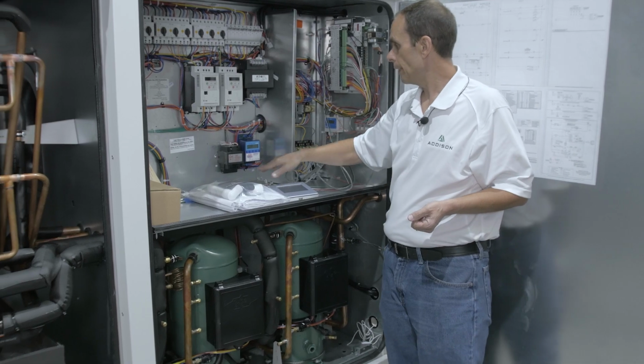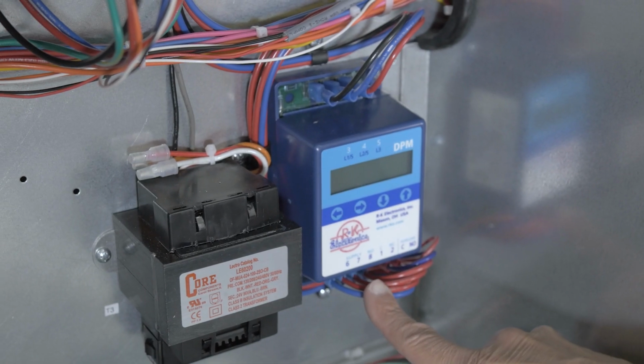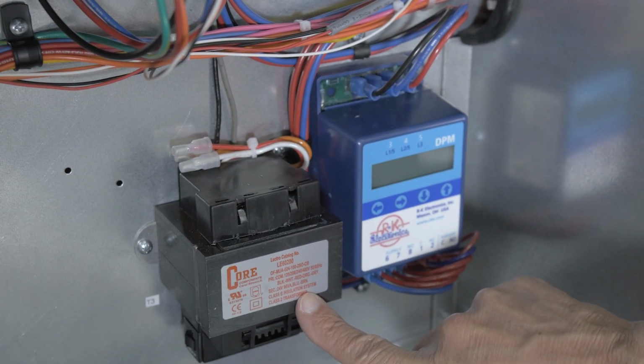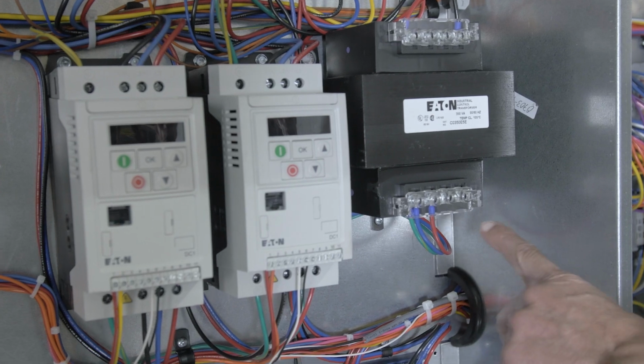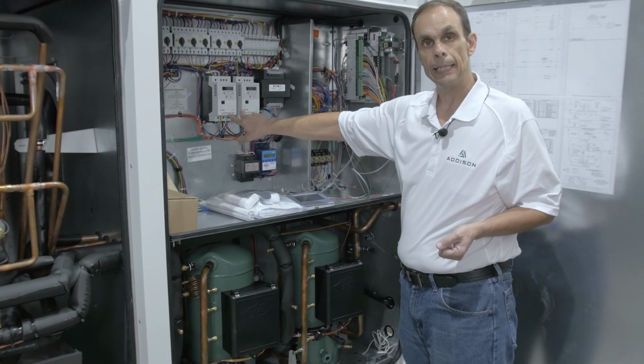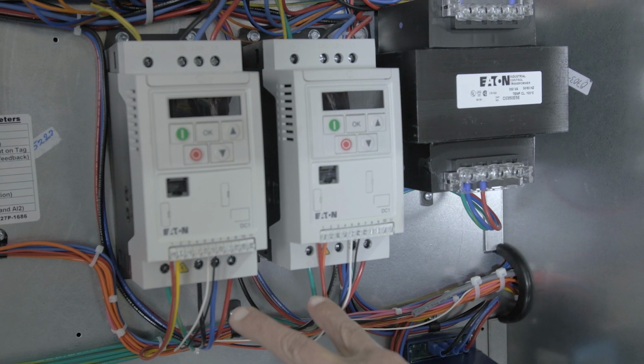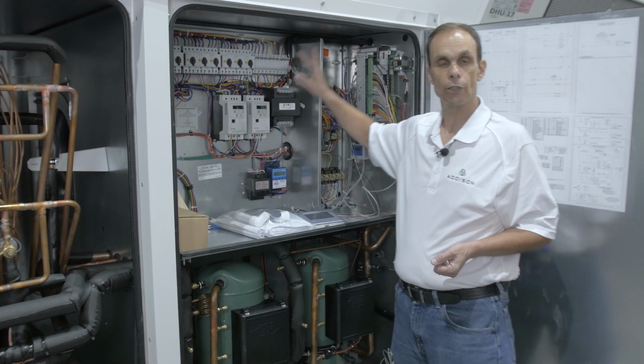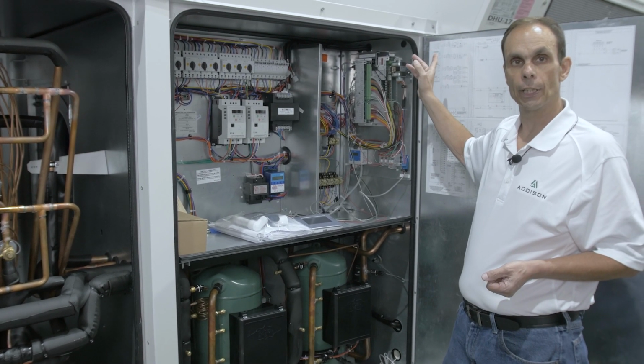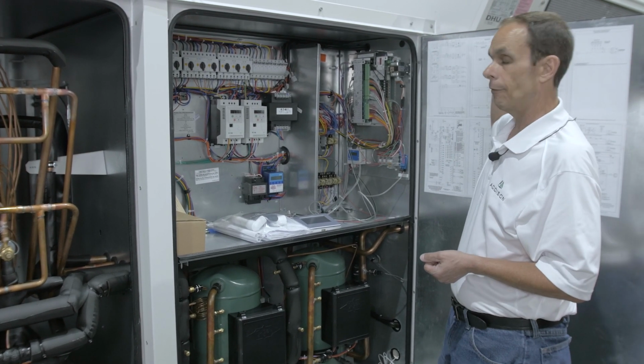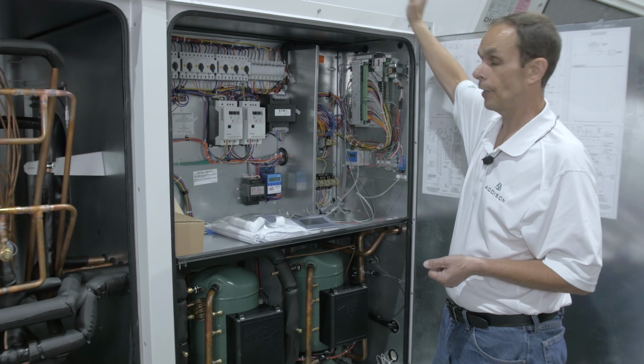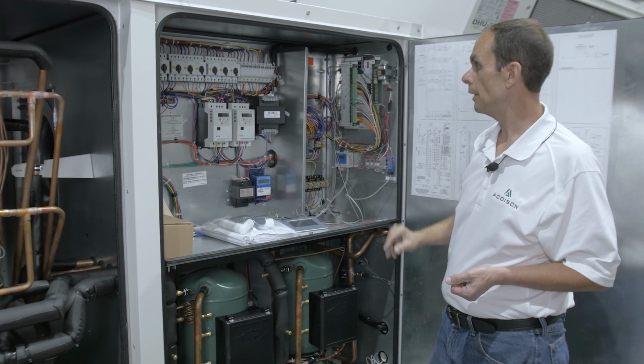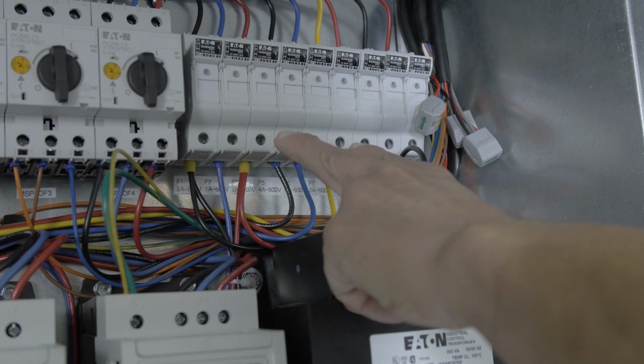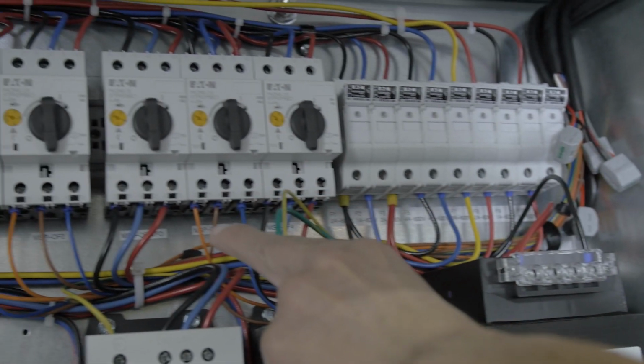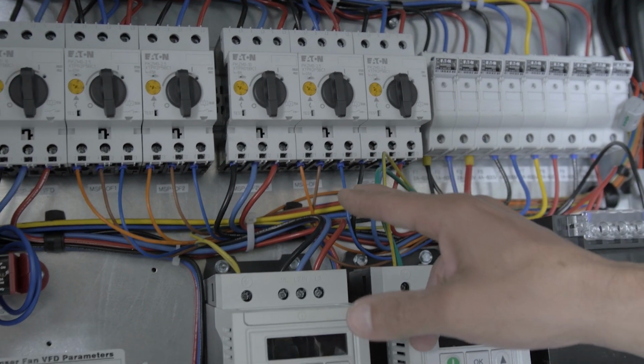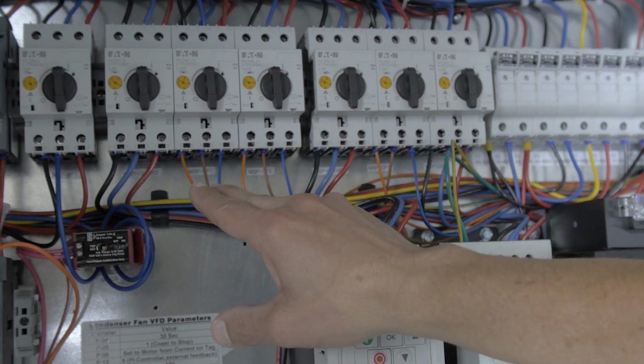In this section over here, you have your phase monitor, your T3 transformer, T1 transformer. Here is an Eaton DC1 VFDs. Both of these VFDs are going to control your stages for your condenser fans. The fans to the right are stage 1. The fans on the left, furthest away, will be stage 2. Up and top are your CC class fuses. To the right here, or to the left, is going to be your MSP overloads.